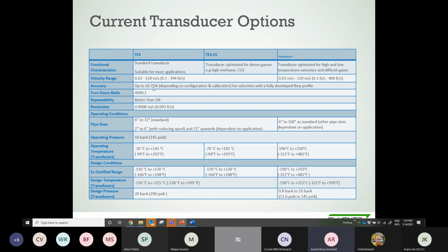So the accuracy varies. Like I said before, we normally go from 2.5 to 5%, but you can get it down to 0.75% if you start doing calibrations and different configurations, especially for dual path. So it's customized depending on the application, really. And in terms of the pipe sizes, we talked about the challenges involving the large pipe sizes. So we can offer meters that are able to measure pipes from 6 inches to 72 inches. And then we have some larger pipe sizes that we can probably achieve with this other meter right here. So I'll talk a little bit about it. In terms of operating pressure, we are normally operating at very low pressure because this is exposed to atmosphere, right? So at the flare level. So 145 psi is the general application.